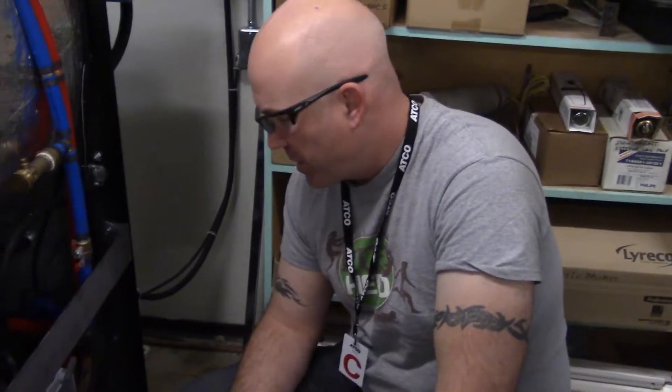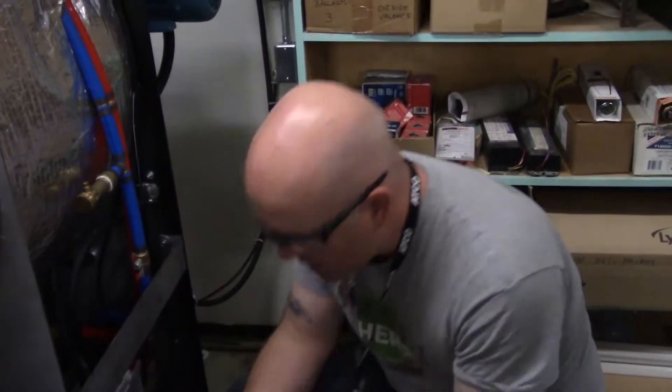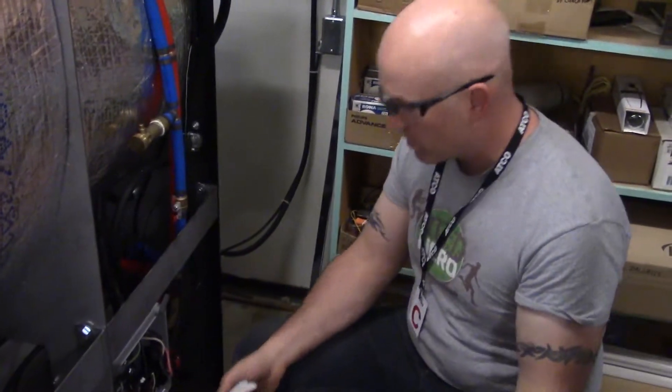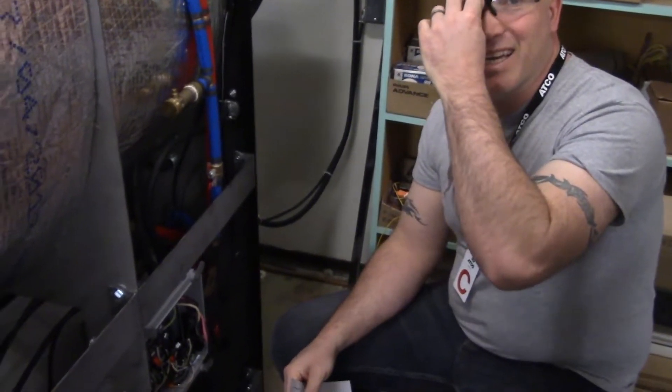Jay, CEO of Installations, what's going on today? This is the last day we're here. We're just finalizing a few minor details to make the folks at Intertek happy. I've got some non-compliance issues that we're just sorting out. I had a standard contactor in here, which meant there was no thermal protection for the motor. So we're changing it out with a contactor that has thermal protection. Just some odds and ends we're cleaning up here. Yeah, just little stuff. It's all minor.